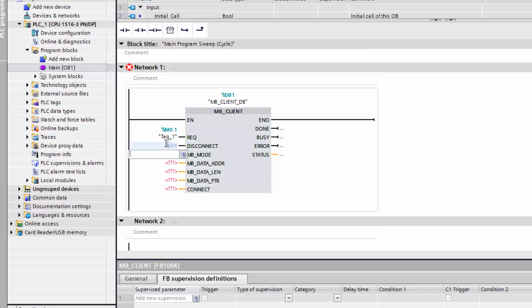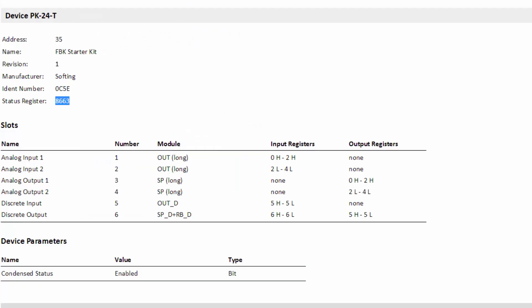The parameter MB_Mode defines the type of the Modbus request. Enter 0 for a read request. In the parameter MB_Data_ADDR, the initial register must be entered from which you want to read. You can find this in the HTML report. In this case, this is 8663.